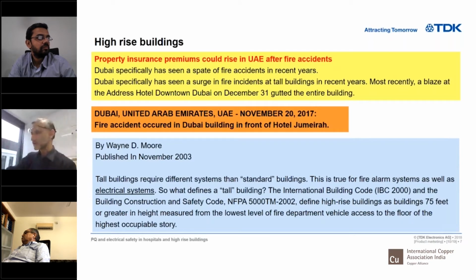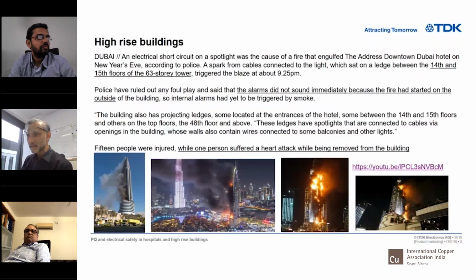You already saw the video clip, so I won't go through it again. Since I saw it in person, I was really impacted. When Manas Kundu asked me to speak, I said, Manas, I was there when the tower opposite Burj Khalifa was burning. It's a 63-story building. The key thing is the alarms did not sound, because the electrical fire and smoke were outside the building, while the alarm system was set up to detect fire inside the corridors and rooms. So until almost everything was burnt, even the fire safety system did not work.